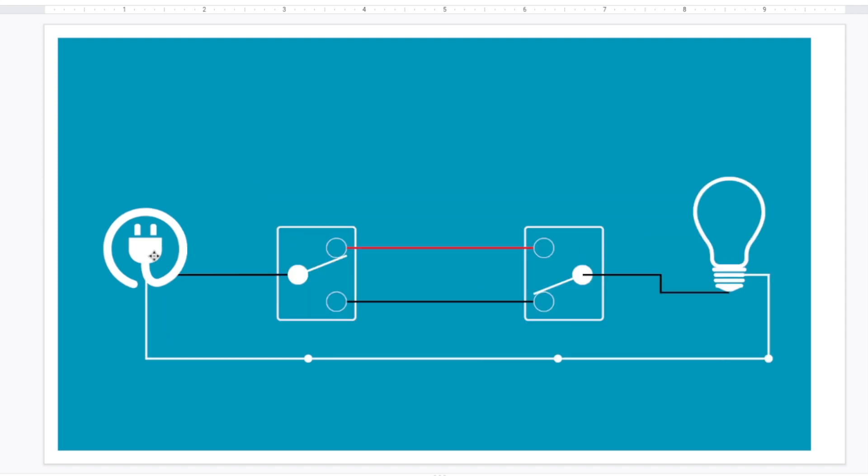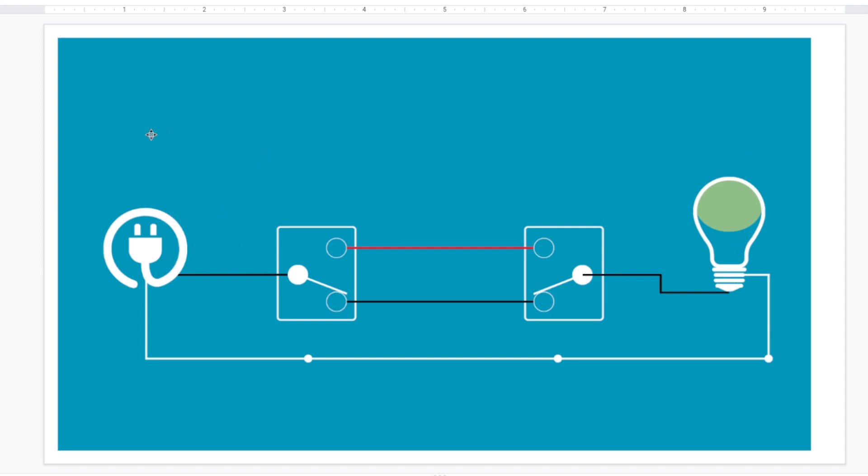So schematically, what does this look like? So here you can see that common terminal, and it's common between these two terminals, which we called the travelers. And depending on the configuration of the light switches, you can see that power is coming to here and stopping here. But if we flick the switch, now our power is traveling down this one, and it's connected to the light through the configuration of this switch. And typically, this is the configuration in which you will find your three-way circuits. It's rare that you will find power coming into the actual lamp. It will be power coming into one of the light switches, going to the next light switch, and finally onto the lamp.